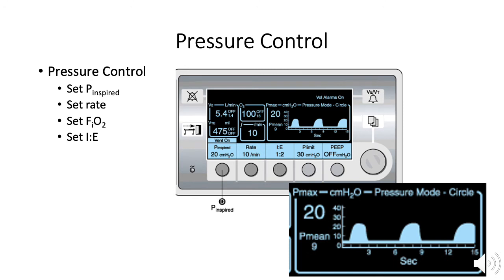Now let's look more closely at the pressure control panel settings. Inspiratory pressure is set at 20 centimeters of water. Tidal volume depends on compliance and is equal to the area under the curve. The waveform has a square shape. Notice that exhaled tidal volume is measured and listed as V-T-E, reported to equal 475 milliliters. The rate is 10 breaths per minute, or one breath every six seconds. The I-to-E ratio is one-to-two; thus two seconds are spent in inspiration and four seconds in expiration. Note the set parameters in blue boxes and the measured parameters in the black boxes above.